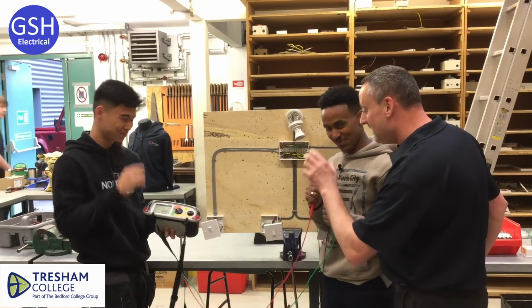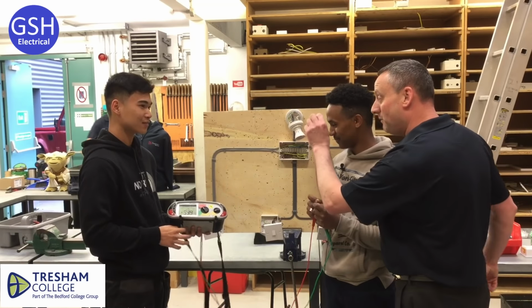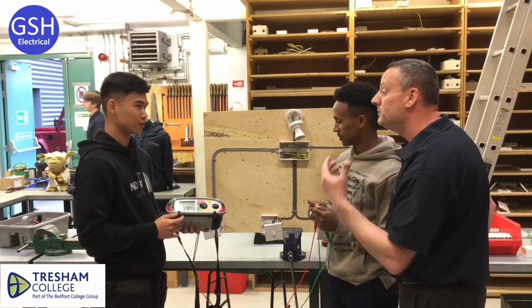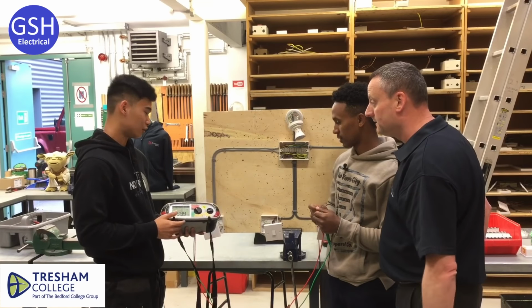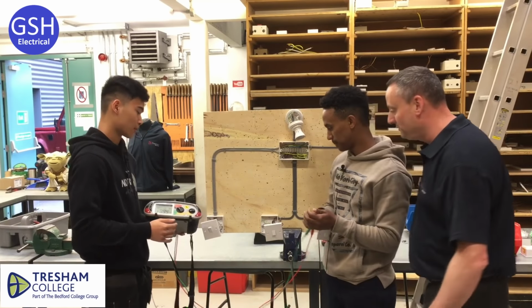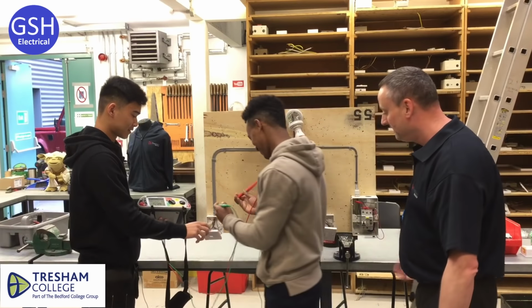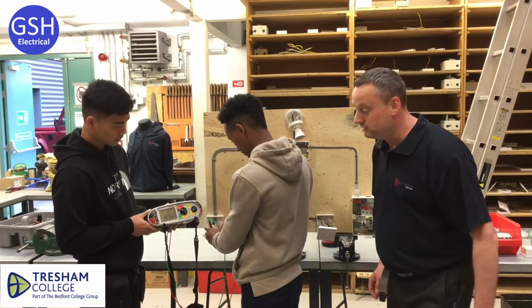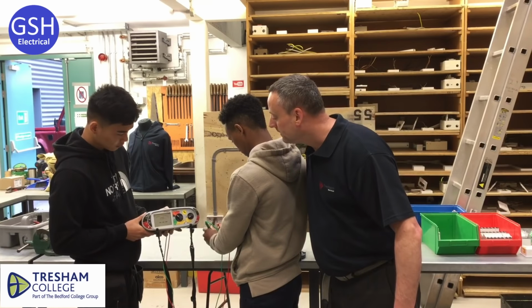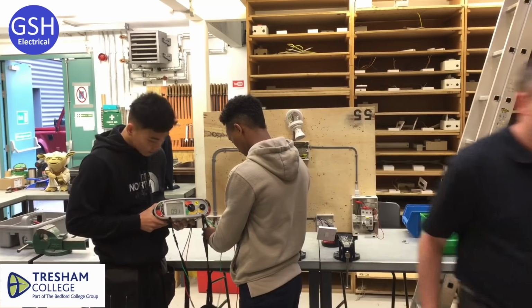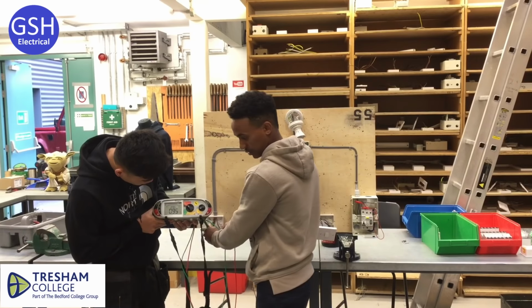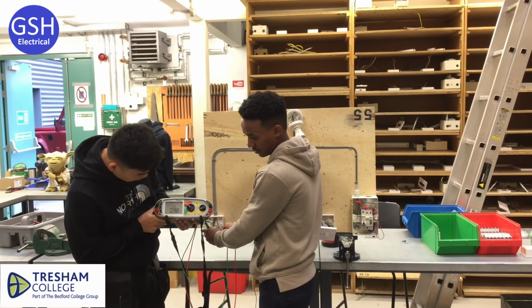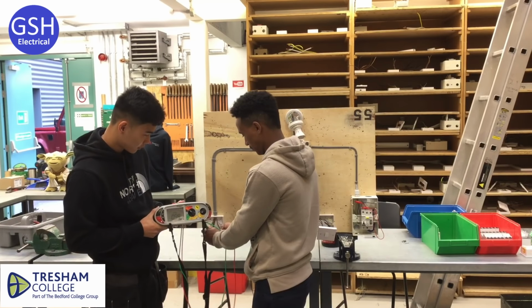Okay, so of all those readings so far, we've remembered 1.28. Where else are we going to prove there is a CPC connected? The switches. We're going to go to the switches now. Let's try that, Abil. Make sure we can keep ourselves in camera, so turn around slightly. And we've got a reading of 0.998. Okay, go to the next one.